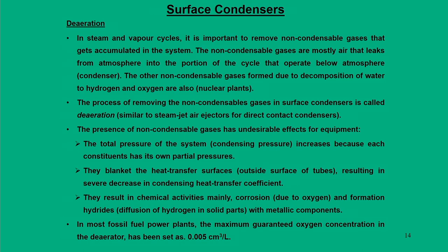This is the first demerit of these non-condensable gases. Second demerit is that these non-condensable gases create a kind of insulation blanket on the heat transfer surfaces, and thereby decrease the overall condensing heat transfer coefficients. So, that is the reason these non-condensable gases have to be removed.